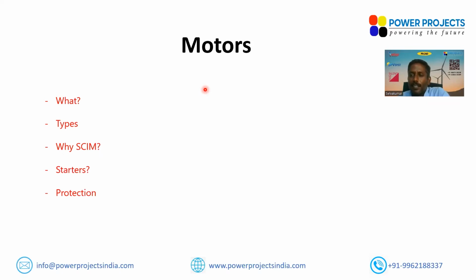Right. So are there any other options? Probably you have another option also. You can convert a slip ring or a squirrel cage induction motor (SCIM) to a synchronous motor. If you're going for a synchronous motor, you're not just eliminating the reactive power consumption, you will be able to generate the reactive power also.